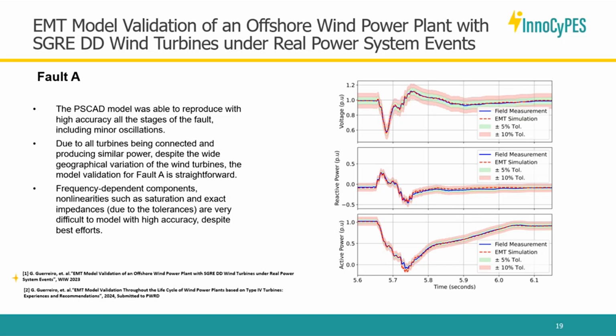This is the response of the plant model for the fault. In this case, validation was relatively simple because the whole plant, all the turbines, were connected at the time of the fault, and all were producing 1 per unit of power, meaning full rated power. This is not so common in a large wind power plant, because usually you have a large geographical area, so the wind is probably not blowing the same across the whole area, maybe 40 square kilometers or more. But in this case we were lucky, and because of that it was relatively simple to validate the model, since we could just use 1 PU for the model.